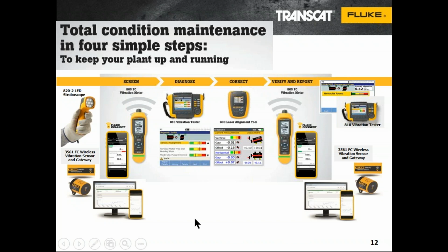The next step, after finding out which machines are good or bad, is to find out what the fault is on the majority of cases and fix it without calling in an expert. These automated diagnostic tools are like a general practice doctor, finding the most common faults: imbalance, misalignment, bearings, and looseness — faults we can fix ourselves. It also tells us how bad it is and when it's time to take the machine down and fix it. Just like a doctor tells us what the problem is and, more importantly, what to do to fix it, that's what this tool does.